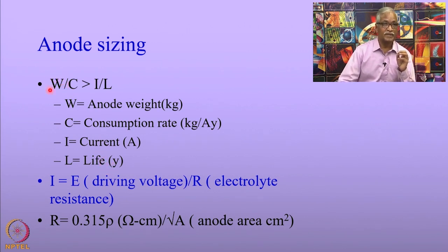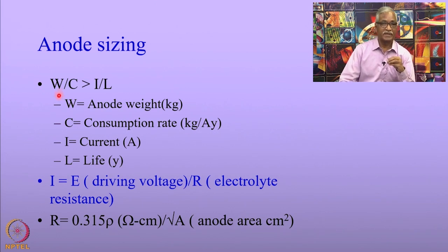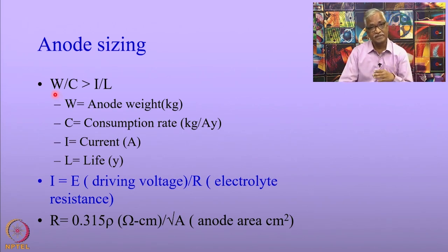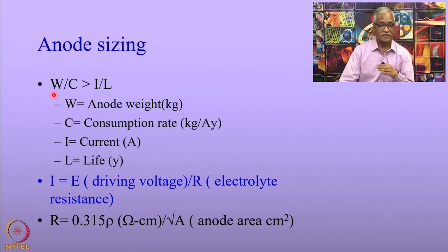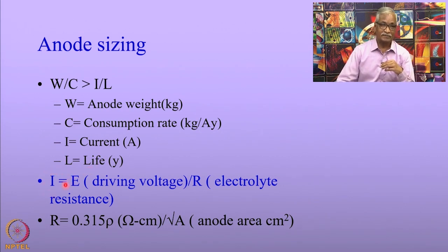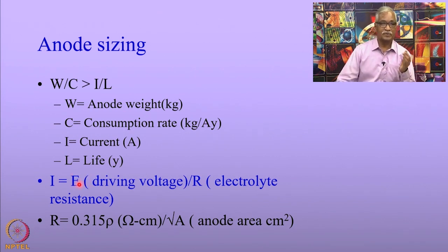The anode size selection also depends upon whether there is adequate driving voltage. The current required is governed by the resistance of the electrolyte, as seen during cathodic protection of pipelines. The driving force of a given anode is known, and it is necessary that the resistance R be adjusted accordingly. There is a relation between R and the area of the anode.